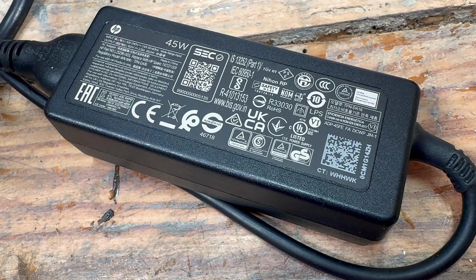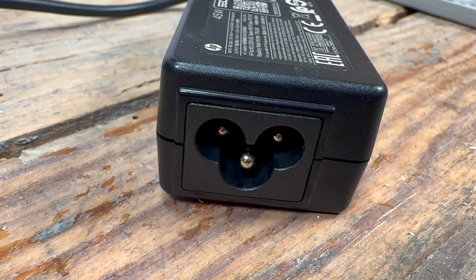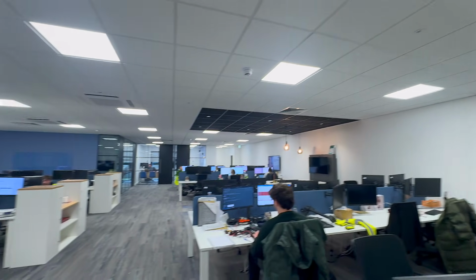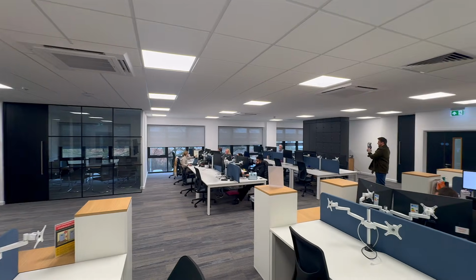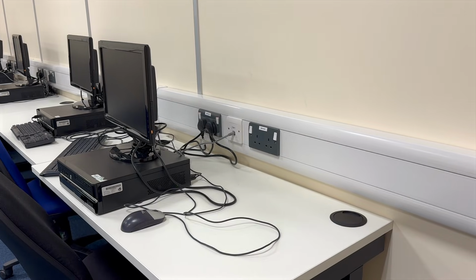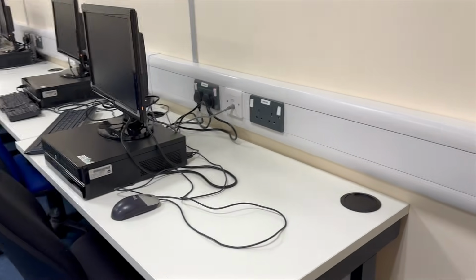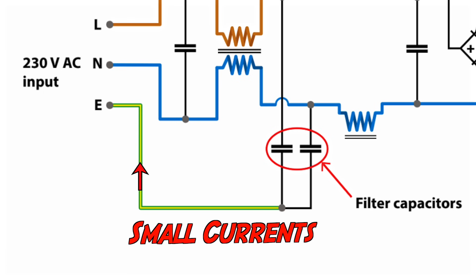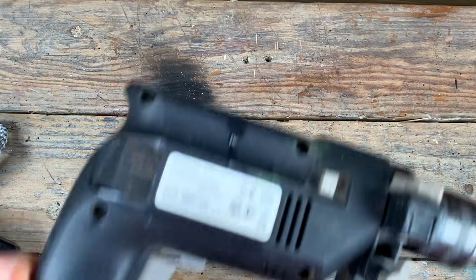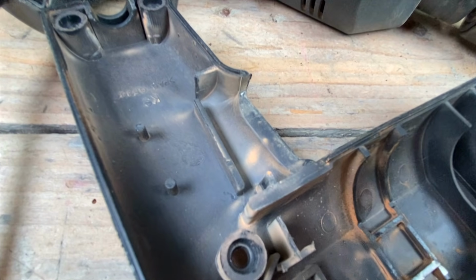Class 2 FE can cause some confusion because at first glance it does look like a Class 1 piece of equipment. It does have an earth connection, but that earth is not used as a protective measure. It's used as a functional earth. The most common examples are switched mode power supplies used in IT equipment. These operate at high frequencies and need filters to prevent interference. Those filters create small currents that need a return path, and the protective conductor provides that path. These leakage currents are normal and expected. Even though the equipment has an earth, shock protection still comes from double or reinforced insulation. The earth supports the filter, not the user.